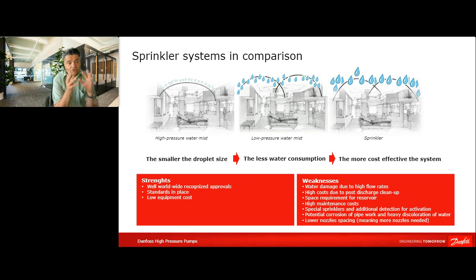First of all, you need much more water to extinguish the same fire compared to a high-pressure water mist. So if you use more water, you have also more water inside that room. So the damage caused by the water distribution is by far higher. So all those cleaning up works and efforts, they are there. And then you also have to allocate space for your pump systems, for your valves, and then for your installation equipment, which is by far bigger compared to a high-pressure water mist system.